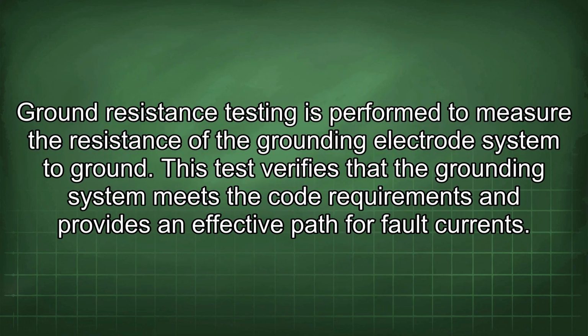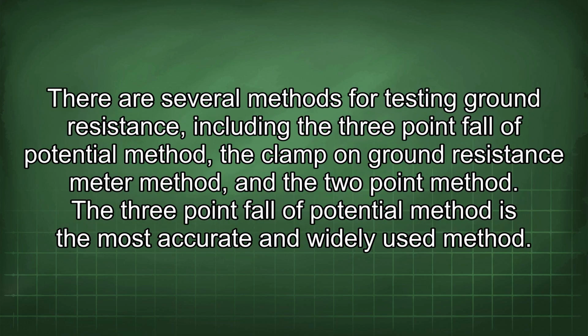Ground resistance testing is performed to measure the resistance of the grounding electrode system to ground. This test verifies that the grounding system meets the code requirements and provides an effective path for fault currents. There are several methods for testing ground resistance, including the 3-point fall of potential method, the clamp-on ground resistance meter method, and the 2-point method. The 3-point fall of potential method is the most accurate and widely used method.